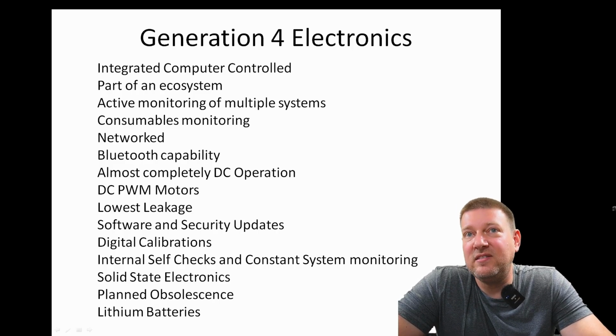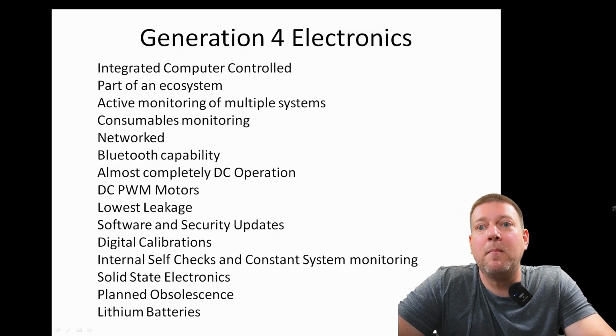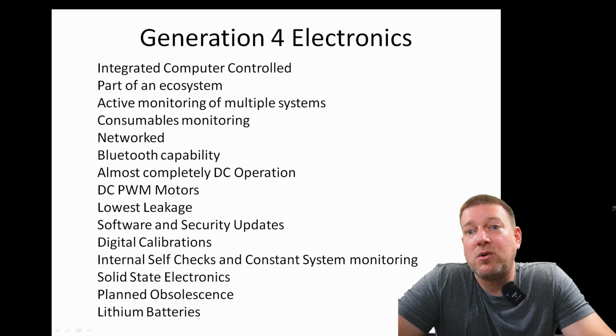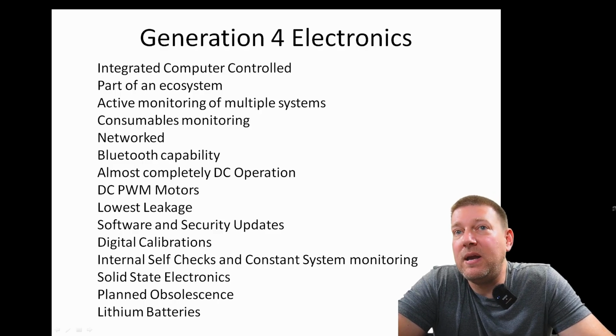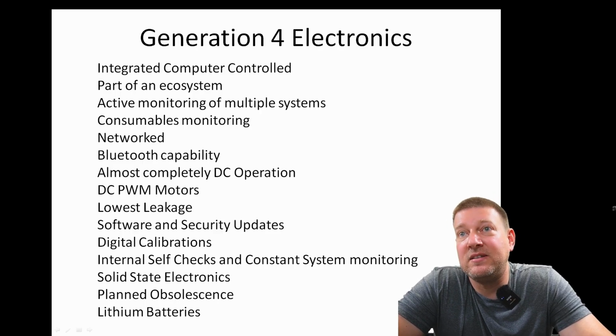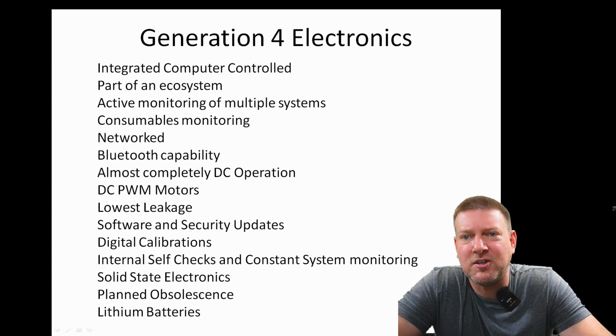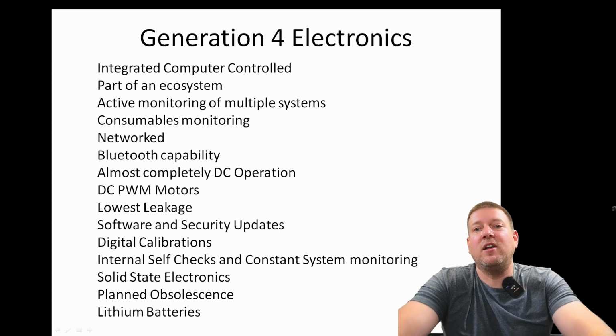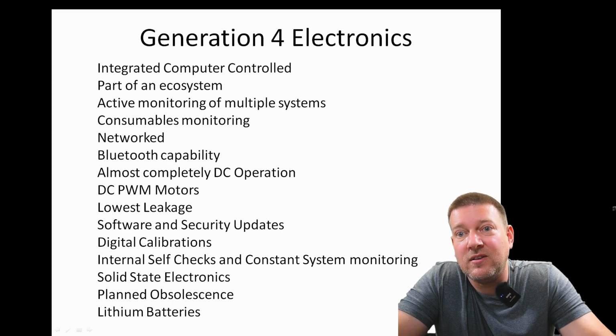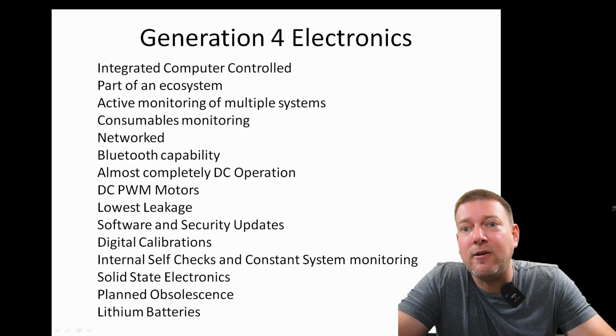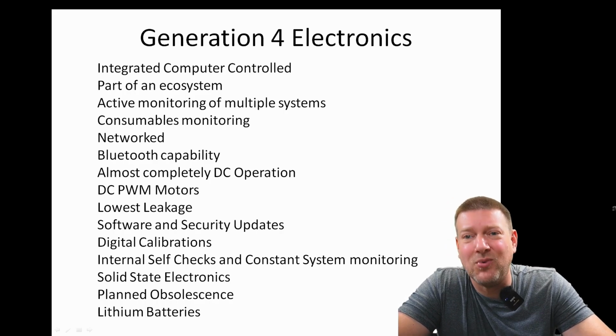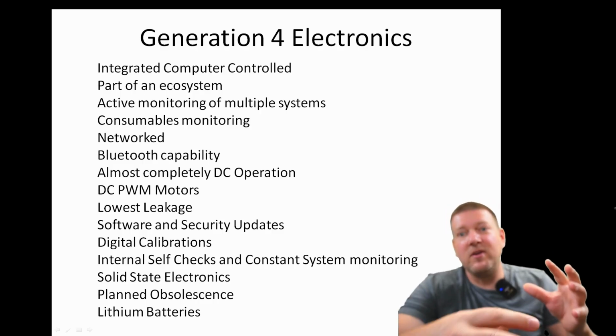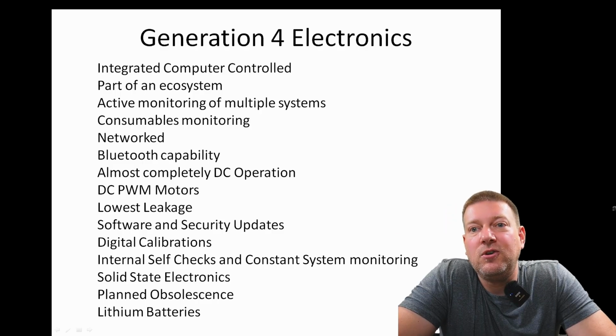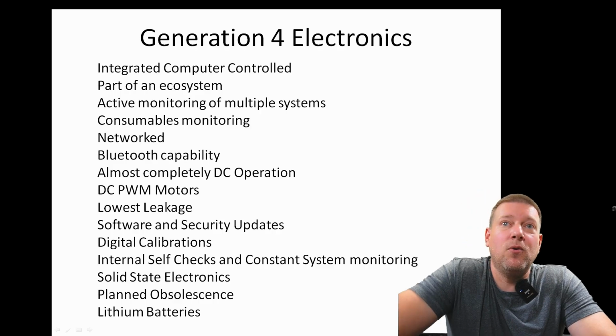We also have DC PWM motors, meaning we control the speed and positioning of the motors using microcontrollers. PWM has changed the game - now we're using brushless motors instead of brushed. Brushes actually create a lot of noise, not just audible noise but radio frequency noise, and that is really bad in medical environments because radio frequency noise can induce itself into neighboring devices. So we do not like that.